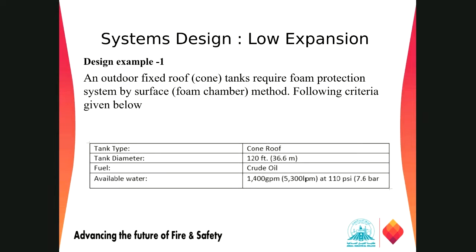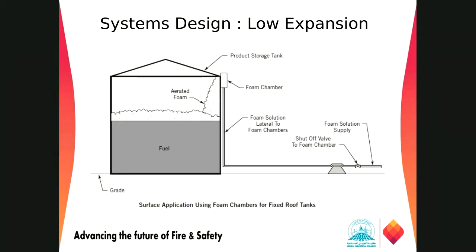1400 GPM at 110 psi from the fire pumps. So what should be the size of the foam system that we are going to discuss now? Here we have a typical schematic for roof tanks. We have a fuel, and from the top, from the foam chambers, it is discharging the foam on the top and extinguishing the fire by displacement of the oxygen, vapor suppression, and the cooling effect.